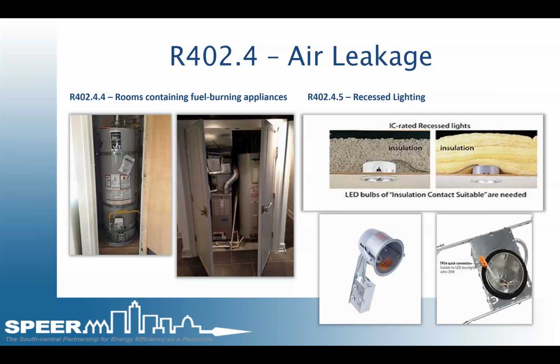Also, R402.4.5, recessed lighting. It states that all recessed lighting must limit air exchanges into the envelope. These must be IC rated, meaning they can be in direct contact with insulation like you see in the photo. Insulation can be put all over the top. And they must be labeled as having been tested with an air leakage rate of 2.0 CFM or less.